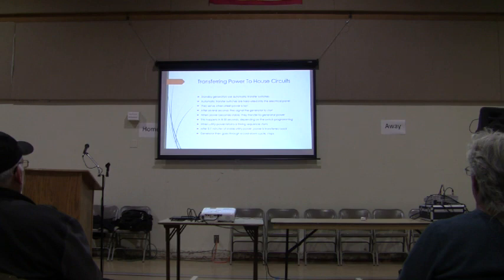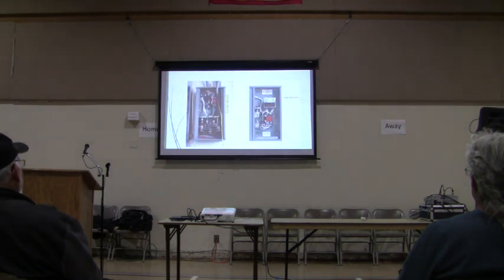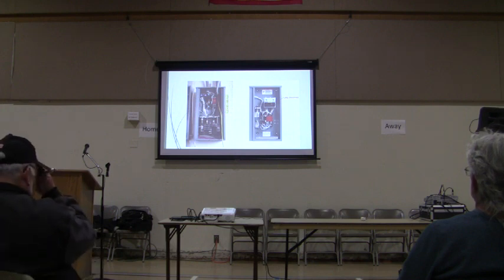Okay? When the utility power returns, it starts another timing sequence. Typically it runs between 5 and 7 minutes to ensure that street power really is back. How many times have we had power come on, it's on for about a minute, and then it shuts back off again, or it's on for a few seconds, and then it drops back out? Well, you don't want the generator starting and stopping like that, so it waits for a bit. And then the generator goes through a cool down cycle. Cool down is very important, because again, it's running at 3,600 RPMs, it's hot. Again, we have our transfer switch.